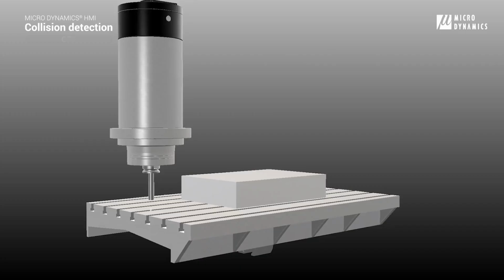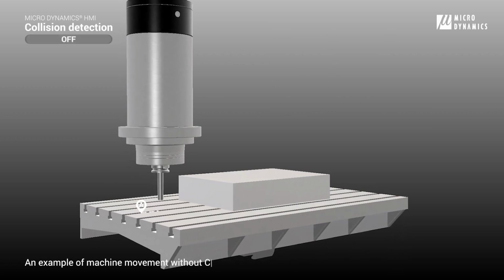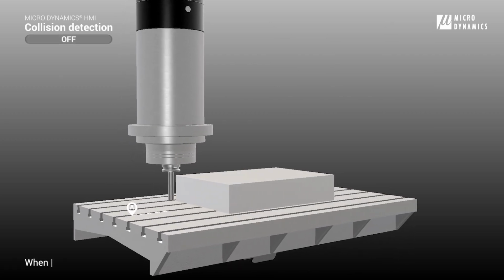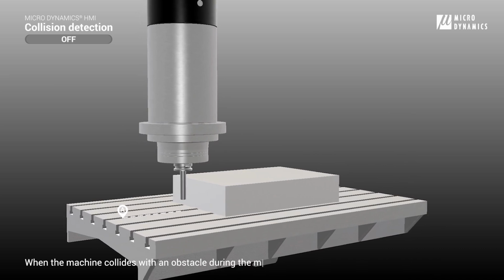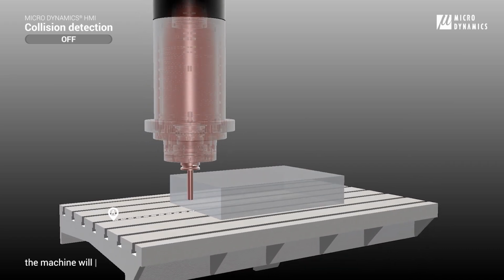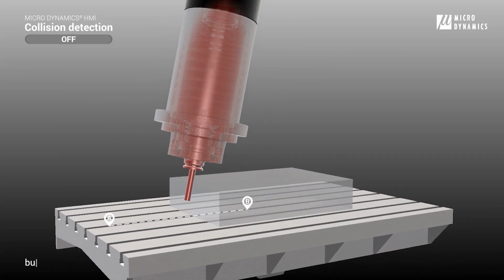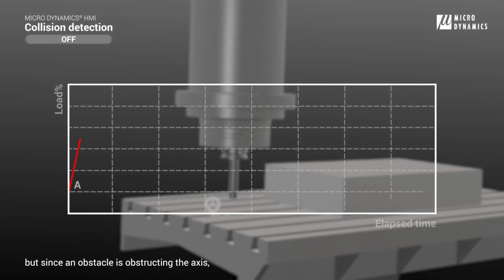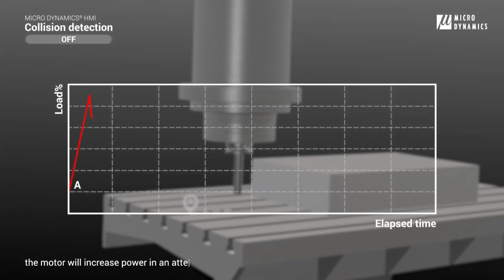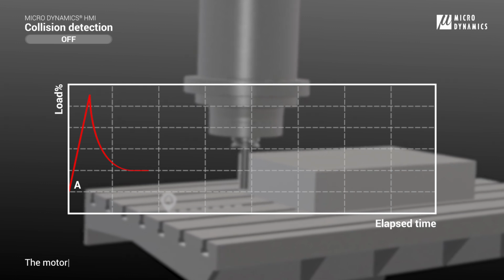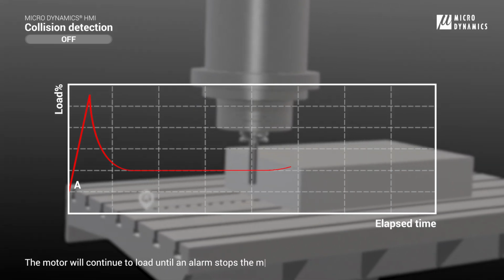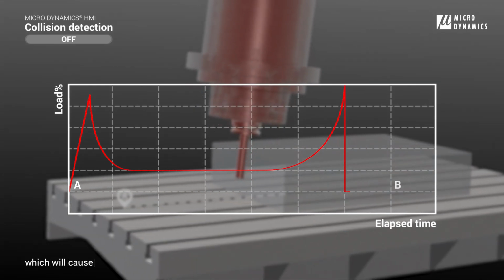An example of machine movement without collision detection function: when the machine collides with an obstacle during the movement from A to B, the machine will continue trying to reach point B, but since an obstacle is obstructing the axis, the motor will increase power in an attempt to continue moving. The motor will continue to load until an alarm stops the machine, which will cause varying levels of damage. Microdynamics collision detection can prevent or reduce damage.